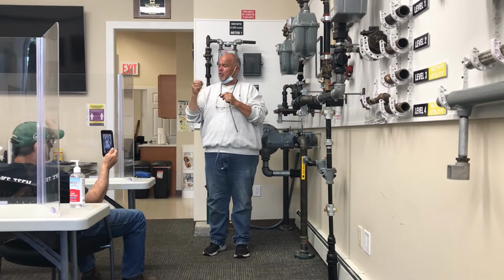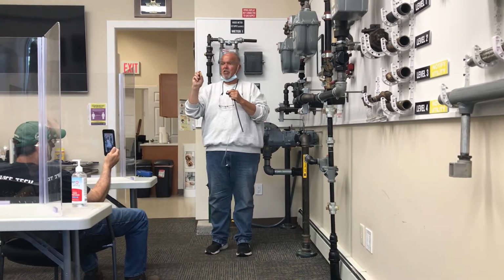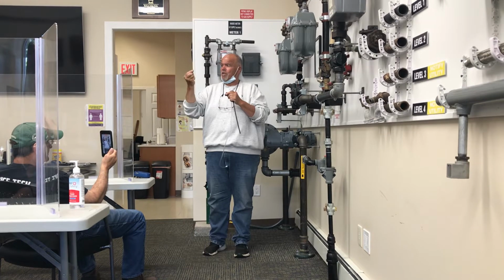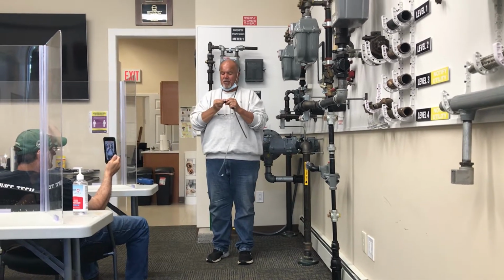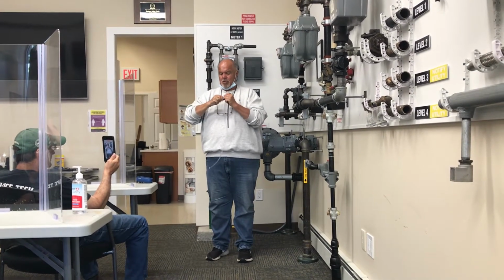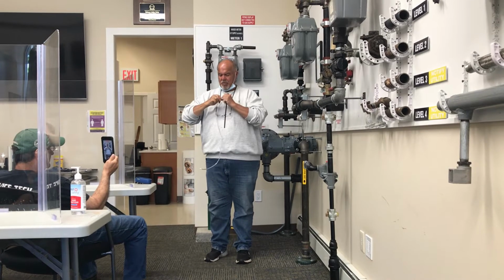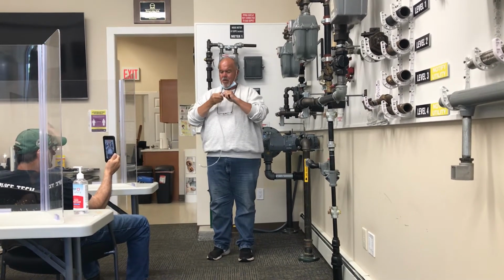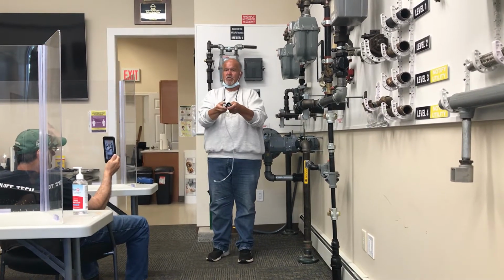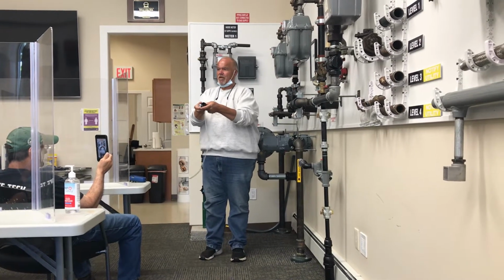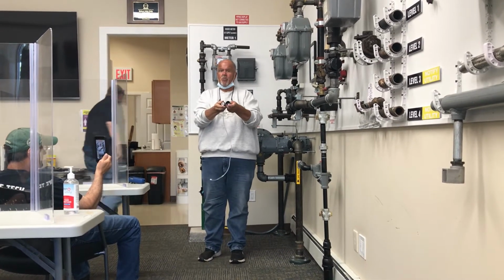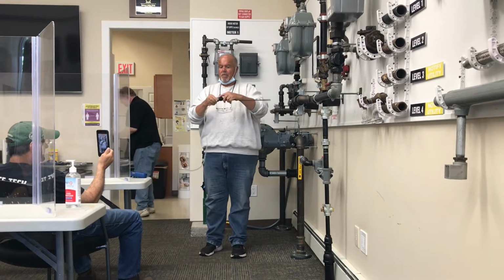You check the filter, it looks clean and dry. No condensation, not dirty, damaged, cracked, or broken. The O-rings look good. You can reconnect it. Reinstall it. If yellow faces yellow, white also faces white. The white side of the hydrophobic filter will face the white dust filter. Reconnect.